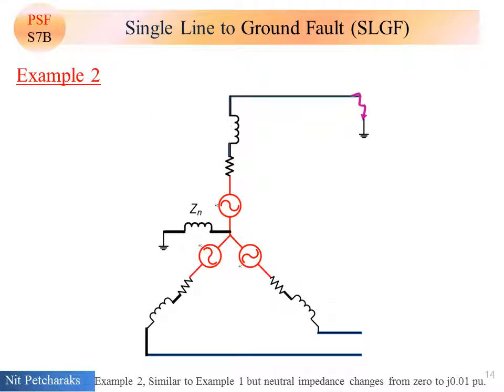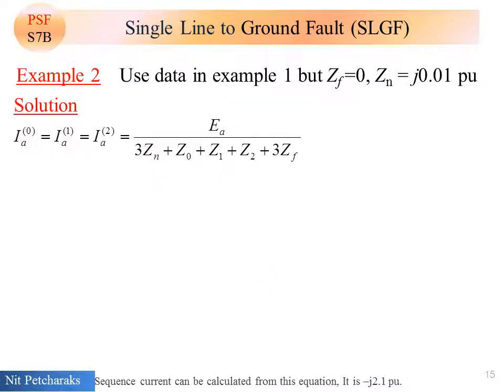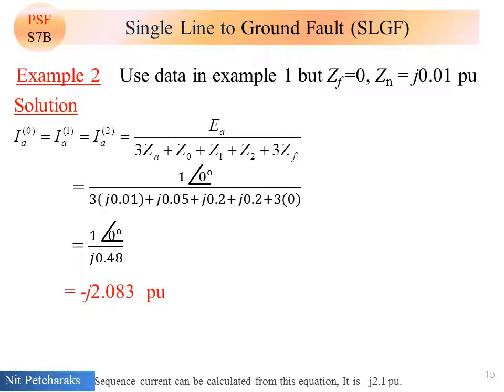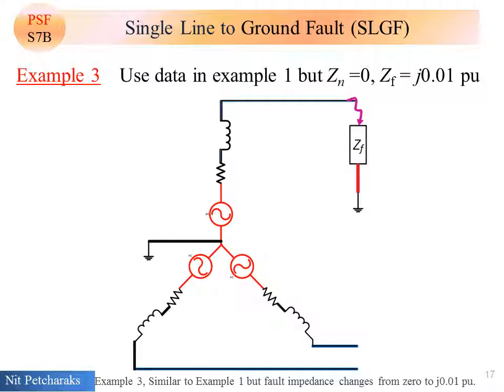Example 2, similar to example 1, but neutral impedance change from 0 to J 0.01 per unit. Sequence currents can be calculated from this equation. It is minus J 2.1 per unit. Then calculate voltage at phase A. It is still zero because fault impedance is zero.